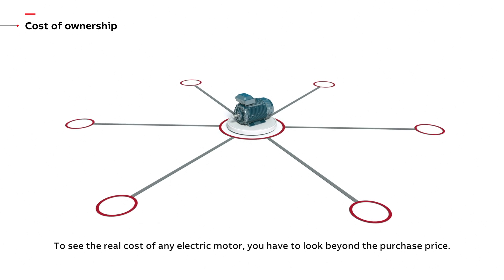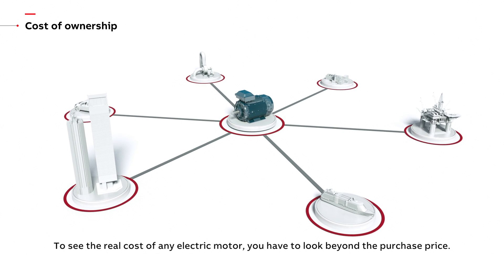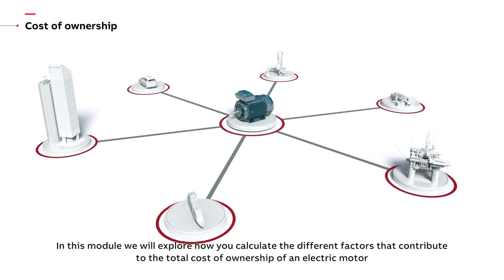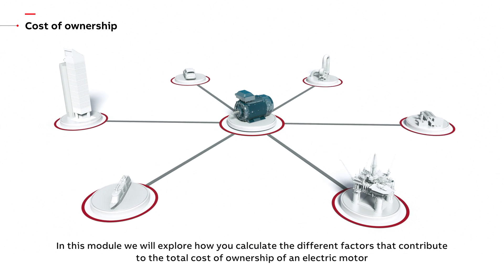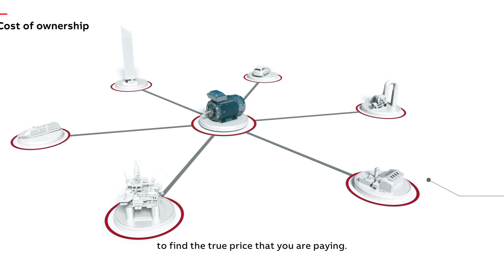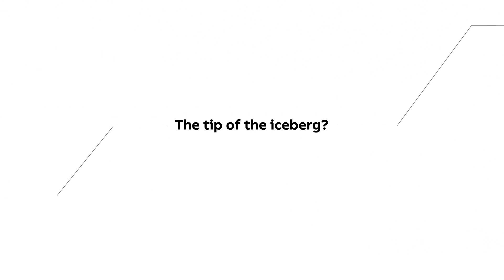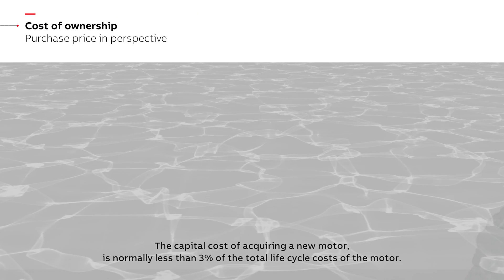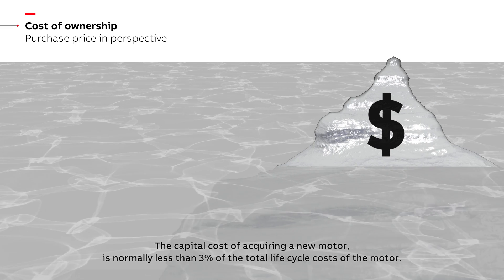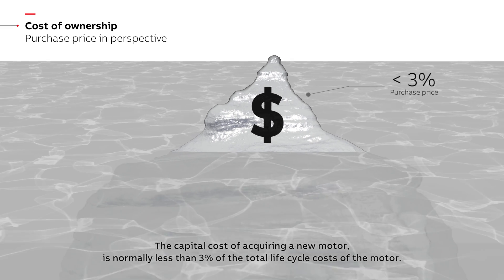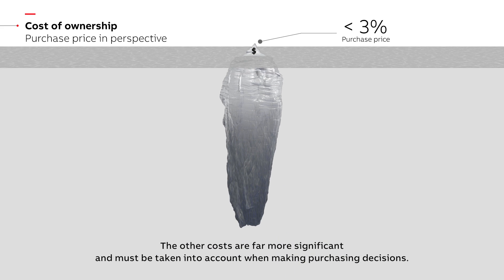To see the real cost of any electric motor you have to look beyond the purchase price. In this module we will explore how you calculate the different factors that contribute to the total cost of ownership of an electric motor to find the true price that you are paying. The capital cost of acquiring a new motor is normally less than three percent of the total life cycle costs of the motor. The other costs are far more significant and must be taken into account when making purchasing decisions.